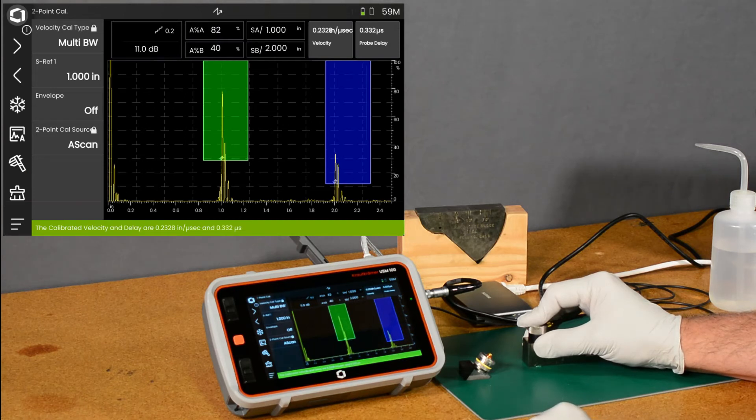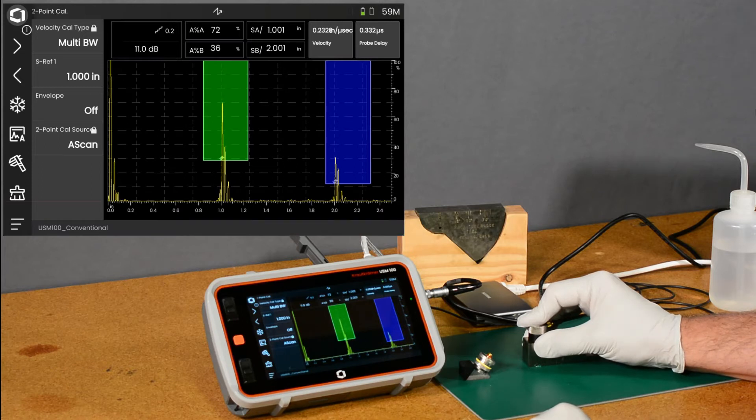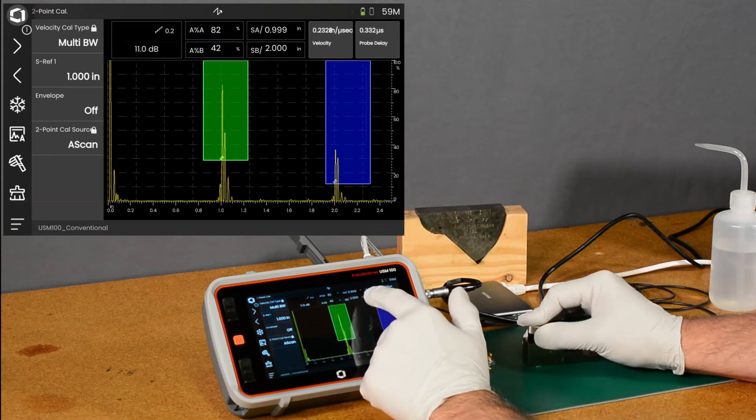and our calibration completes. And it looks like we measured 0.2328 inches per microsecond of velocity and 0.332 microseconds of delay.